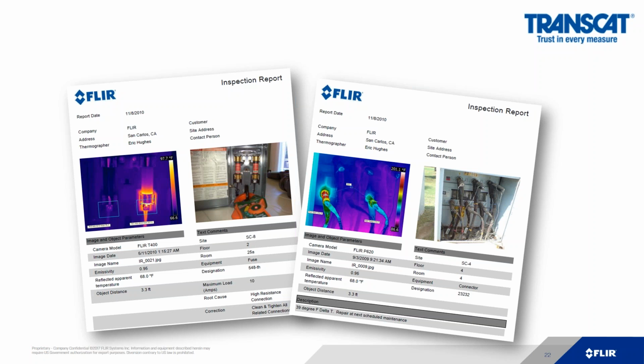Many thermal cameras out there both take a thermal image and a visual image, as we can see these 2 images side by side. The value is it gives a complete description of what's hot and what could possibly cause the problem. In software, we also have the ability to analyze more than just the 1 pixel that we were looking at before. We can measure all the pixels. We can adjust the contrast and brightness. As long as we have the picture in focus when you took the picture, you can analyze it after the fact and change palettes, change measurement spots, and you can help build the return on investment and reporting for either your customers or your managers if you had to repair a problem you discovered with the thermal camera.